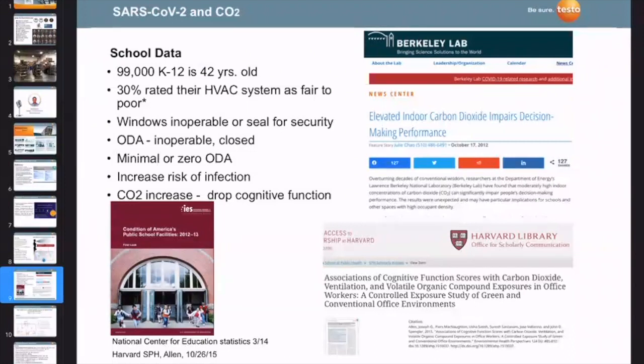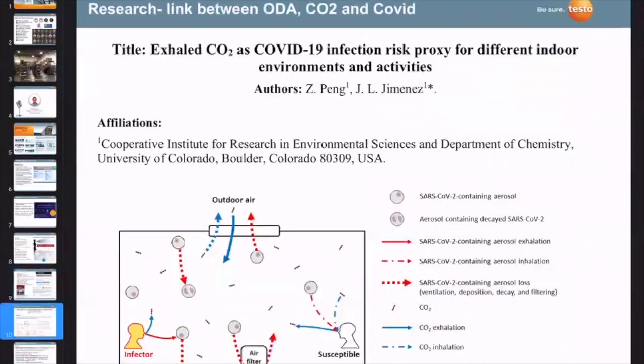At the same time, looking at the relationship CO2 has with COVID-19, the lower amount of fresh outdoor air we can bring into a building space like a school results in a higher CO2 number. So the proxy to COVID-19 is that if you've got elevated CO2 levels, you probably don't have enough fresh outdoor air to dilute that airflow volume, which would otherwise reduce the risk of transmittance by mixing more fresh air with the room air in the space.